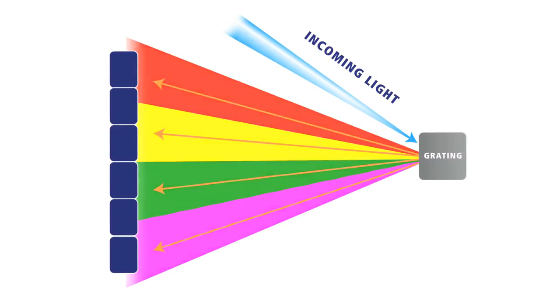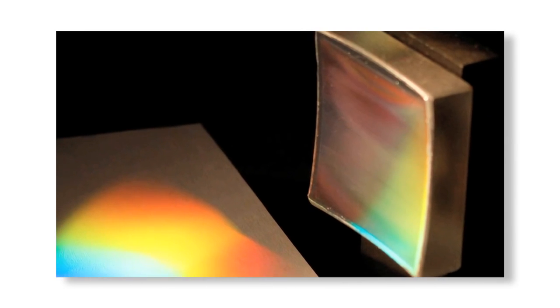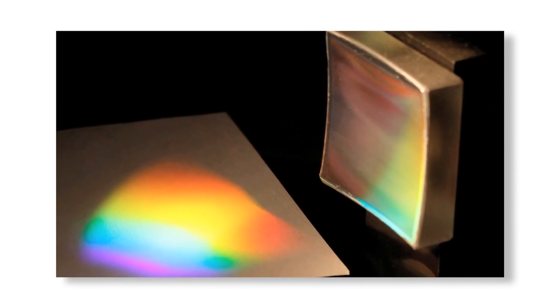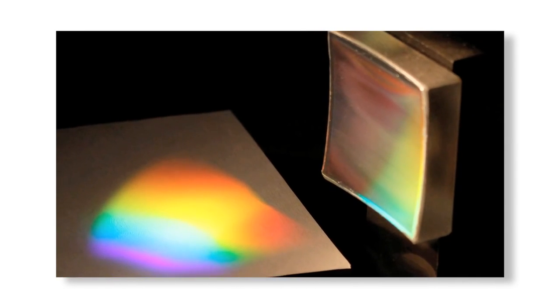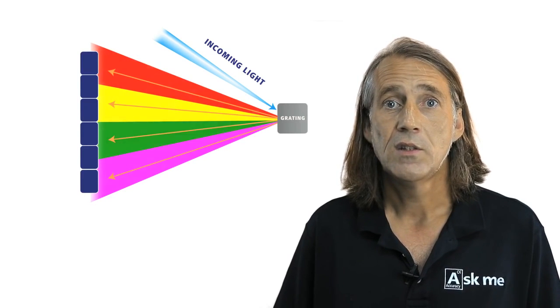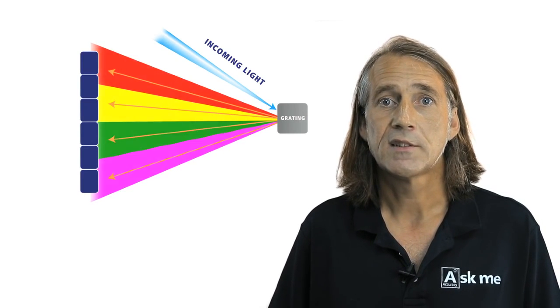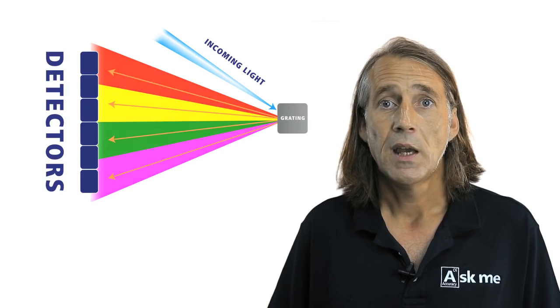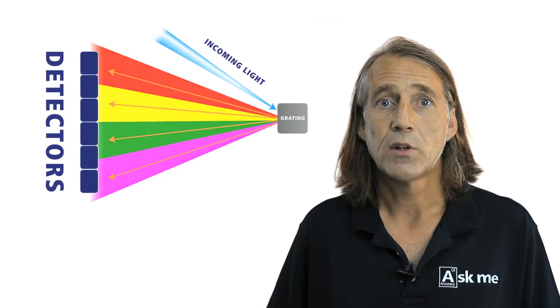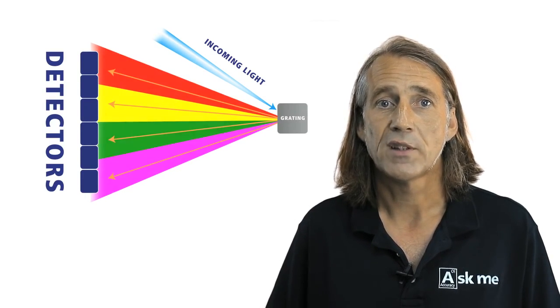The characteristic light emitted by the atoms in the sample is transferred to the optical system, where it is split into its spectral wavelengths by a high-tech grating. The grating contains up to 3,600 grooves per mm. The individual spectral line peak signals are then collected by detectors and processed to generate a spectrum showing the light intensity peaks versus their wavelengths.